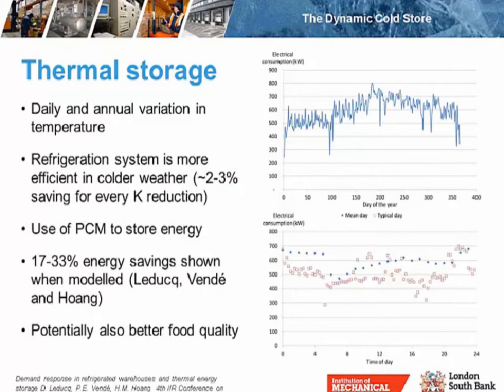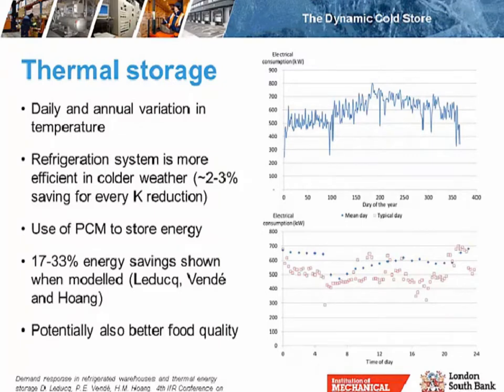Pat will also talk a little about phase change materials. There's also another benefit: potentially better food quality. In chilled stores, you can't load shed in the same way as frozen stores, because you can't reduce the temperature and freeze the food — you have a much lower margin of temperature range to operate over. Whereas in a frozen store you can reduce the temperature, but for some foods it's not ideal to fluctuate temperature too often. If you can maintain temperature at a more stable and lower range of fluctuations, you can potentially get better quality for some foods.